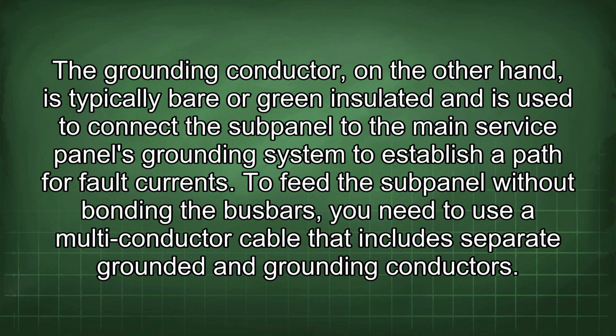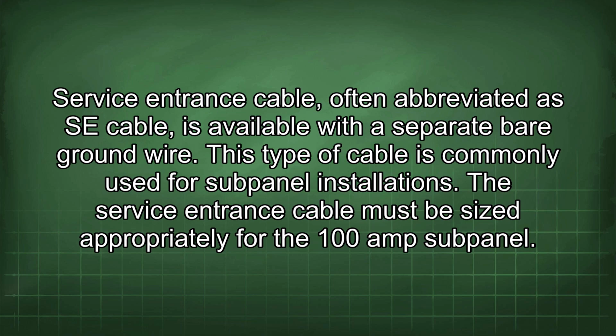To feed the subpanel without bonding the bus bars, you need to use a multi-conductor cable that includes separate grounded and grounding conductors. Service entrance cable, often abbreviated as SE cable, is available with a separate bare ground wire. This type of cable is commonly used for subpanel installations.